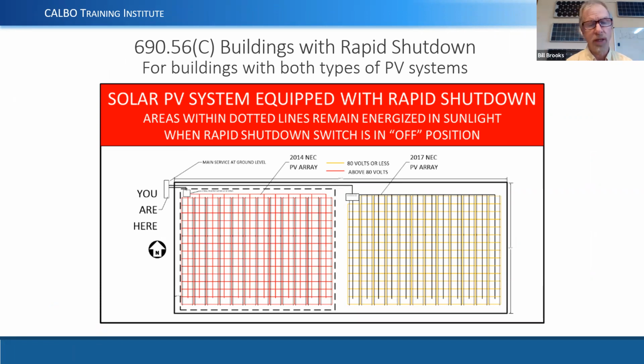There's some very large homes in the Tri-County area. And so if we have an older system that's been installed under one version of the electrical code, and then we have a newer system that's got to be installed under the current 2019 California Electrical Code, then the code requires us to have a plan view of the roof showing what is still energized. The dotted line shows areas that remain energized after throwing the rapid shutdown switch, turning the switch off.